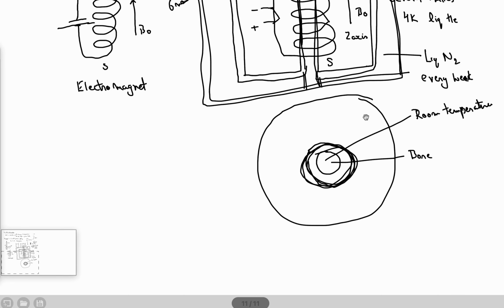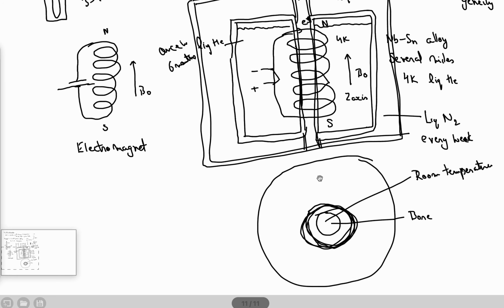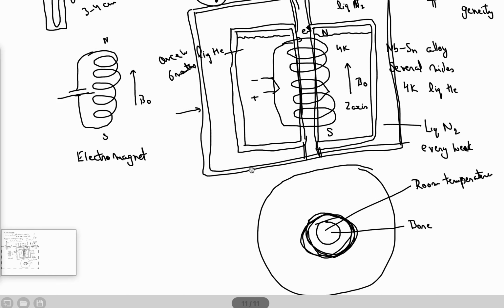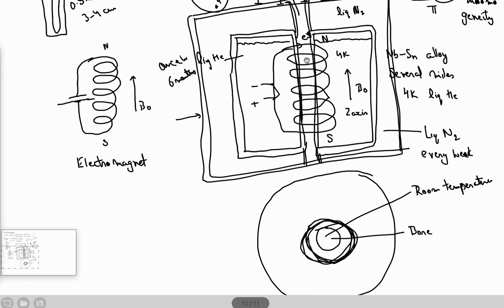Okay, so your overall assembly, the outside of this is also maintained at room temperature, so you don't feel it cold. Only the inner temperature, here it is liquid nitrogen temperature, and here it is 4 Kelvin temperature, right? Liquid helium temperature. Okay, so now you have charged the magnet and maintained the magnet at the B0 magnetic field, let's say 11 Tesla or 14 Tesla.